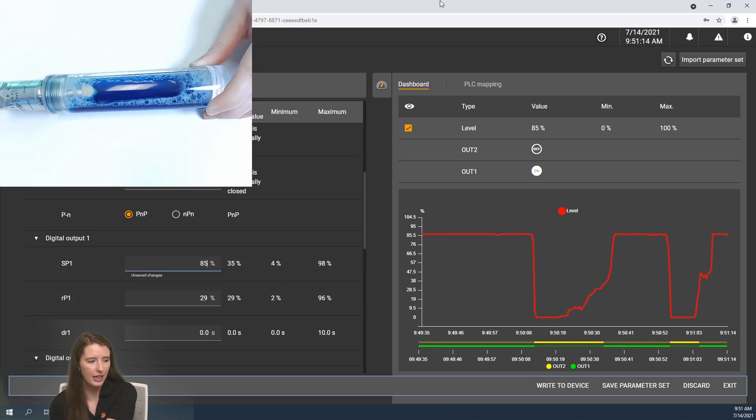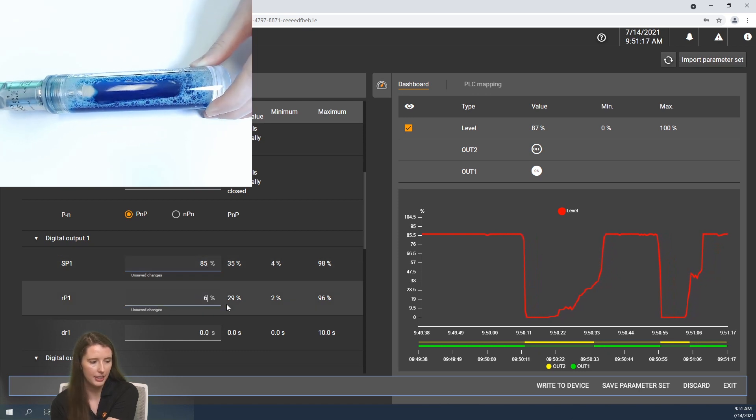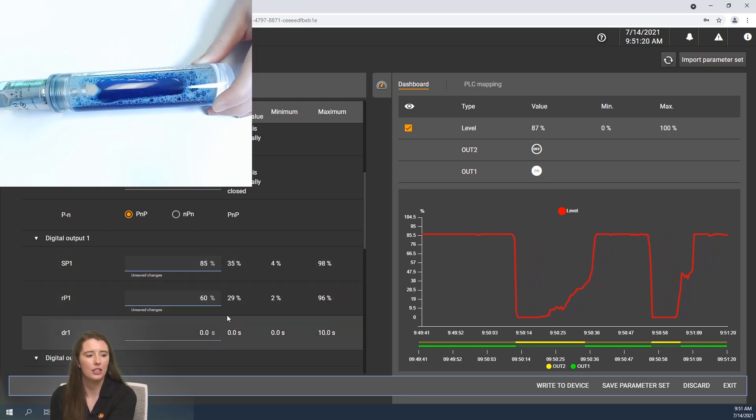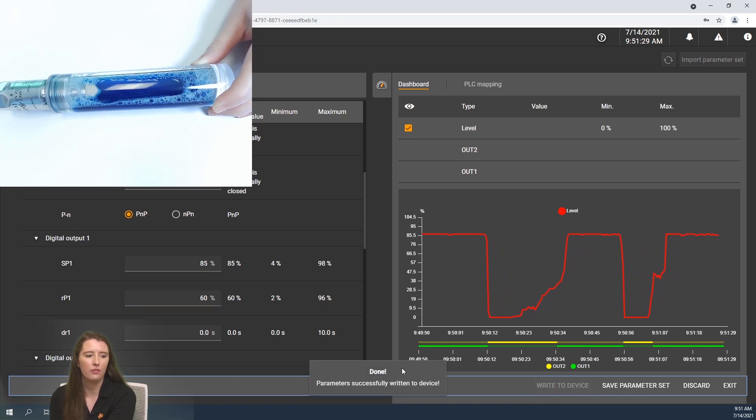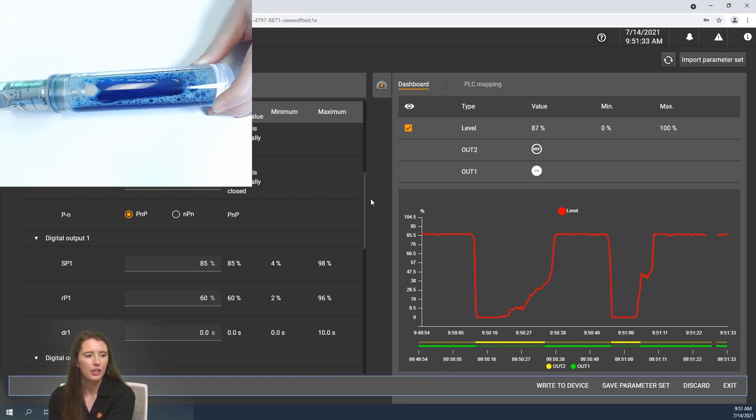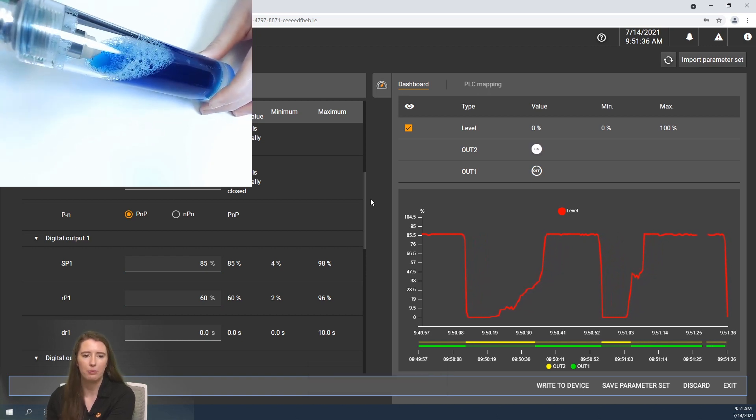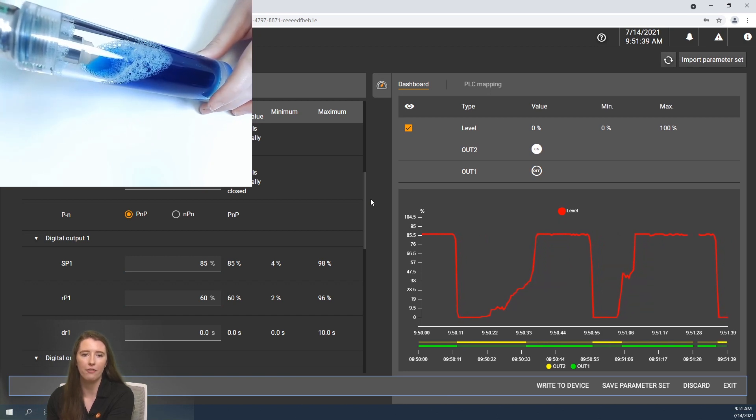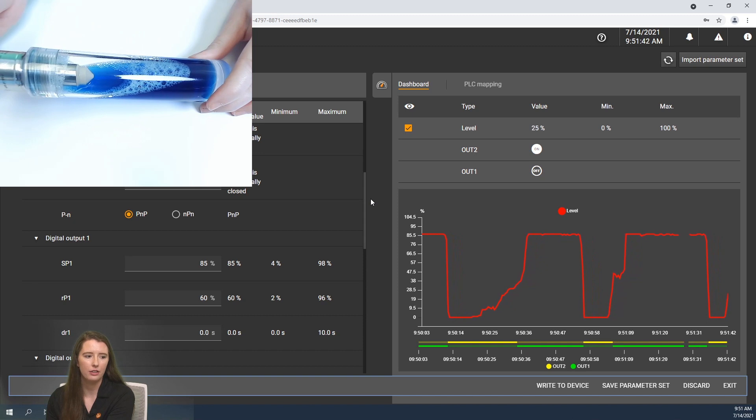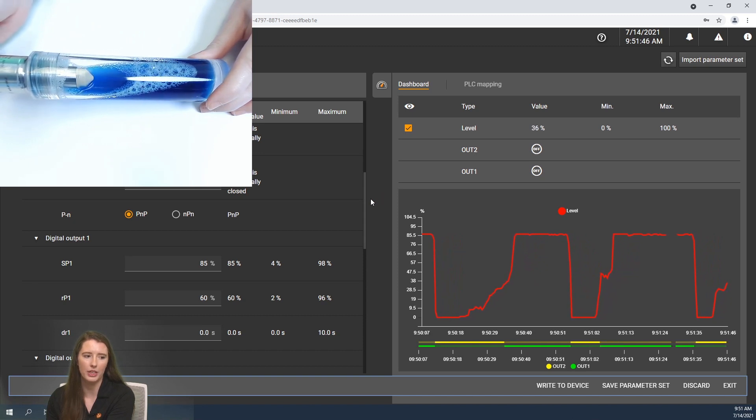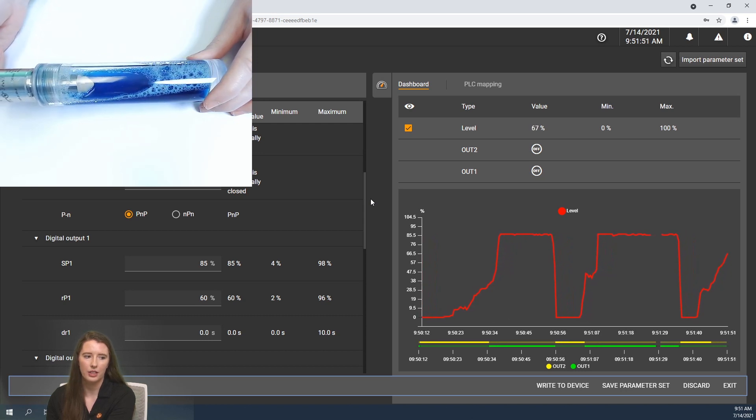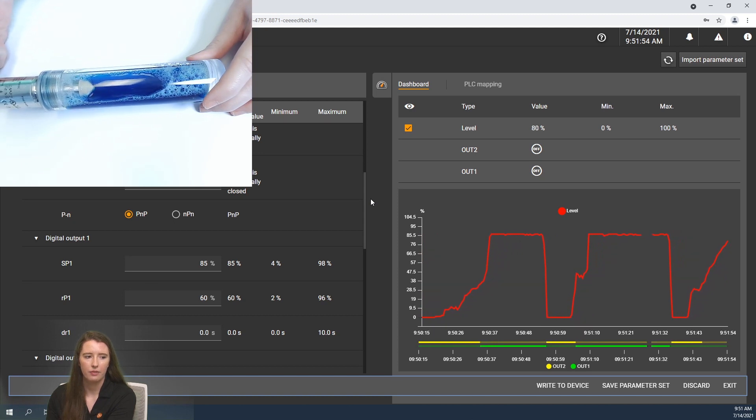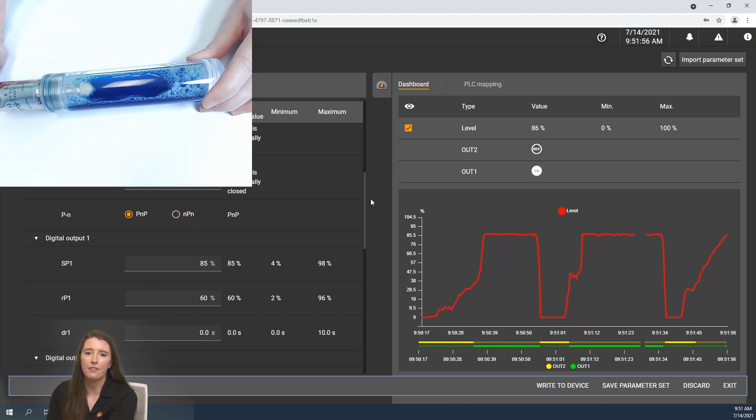Now if I want to change those settings, for example I can set it for 85% and 60%. Once you write those settings into the software you will then go to the bottom right hand corner where it says write to device and if I click on that it'll write those parameters to the device and let me know when that has been done successfully. Now if I take the sensor back out of the media and it is reading zero, output 1 is off again. And if I slowly lower it, even though 35% has been reached, output 1 is still not on until it reaches 85%.